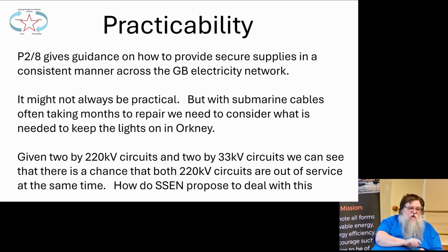It might not always be practicable, and with submarine cables often taking months to repair, we need to consider what is needed to keep the lights on in Orkney. Given 2 x 220 kV circuits and two 33 kV circuits, we can see that there is a chance that both 220 kV circuits are out of service at the same time. And a question I've put is, how do SSEN propose to deal with this?